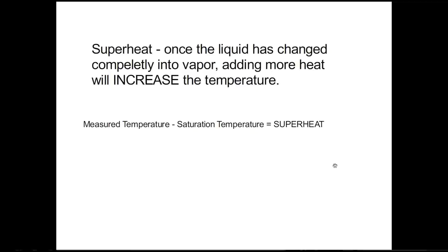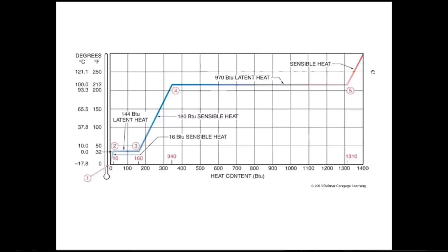All right, superheat. Once that liquid, in this case water, but refrigerant as well, once that liquid has changed state completely into vapor, adding any more heat will increase the temperature. Now, that's where we talked about right here. We have changed the liquid vapor combination into 100% vapor. Any heat that is added, this is our superheat. Any heat that is added is called superheat, and this is where this happens. So that is this part of the chart right here.